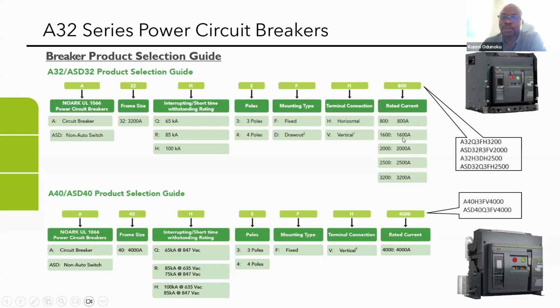Whatever current you select here, we will automatically match the rating plug of the trip unit with that current. But you have the option to select a lower value in situations where, for example, your system is being considered with future expansion, but right now the facility itself is not using up to that current capacity. So you can use a lower rating plug for your trip unit. And this is an example of the sort of part numbers you can get when you follow this.